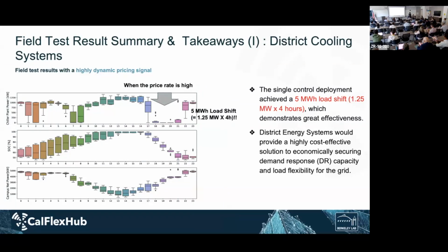This is the field test result for a cooling plant. The first figure shows the chiller plant power, which includes only the 5 chillers and the cooling tower pumps. This is the state of charge, representing the height of the chilled water stored in the tank. The last figure shows the campus net power, including the chiller power plant and all other power consumption in the buildings.